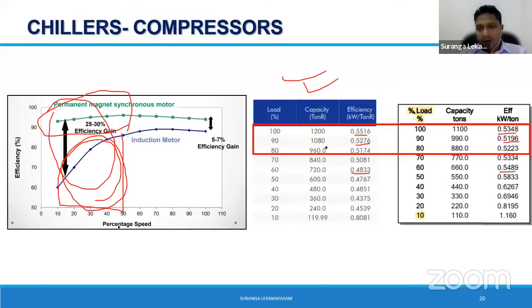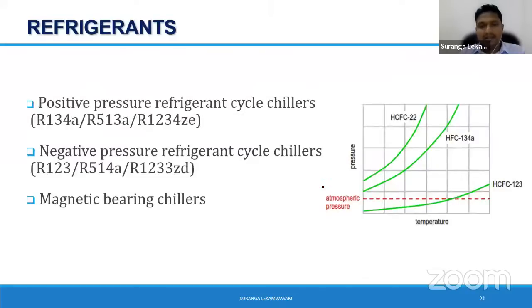But if you have a flat load, mostly like in garment factories, their loads are mostly flat because their cooling load is derived mainly from internal loads, machine loads, occupancy loads, etc. So there's no point in installing these by spending much more capex, because these are very expensive machines, right? If the building or the machine runs closer to 100%, you don't get much saving. Even if you get a saving, it is not substantial. Therefore, you have to wisely select these machines according to your requirement. So that is the challenge for the consultant or the designer, rather than bringing things in blindly.